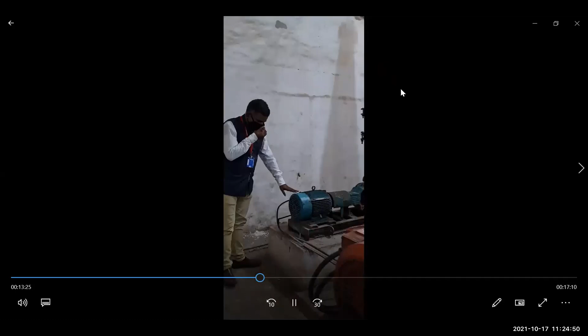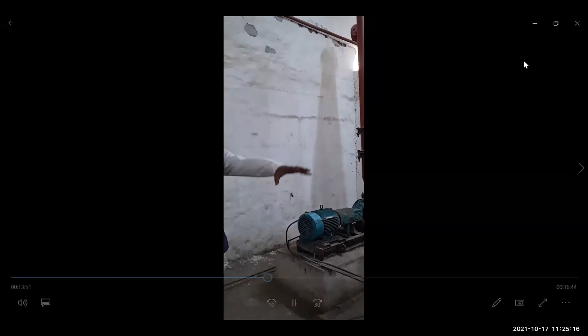This is the jockey pump. The jockey pump is normally used to maintain the pressure required at the water line. We just saw the sprinkler line and hydrant. So in those lines, to maintain the pressure, we normally use these jockey pumps. Now all these three pumps are operated and controlled through this panel. Now we'll see how this works practically.